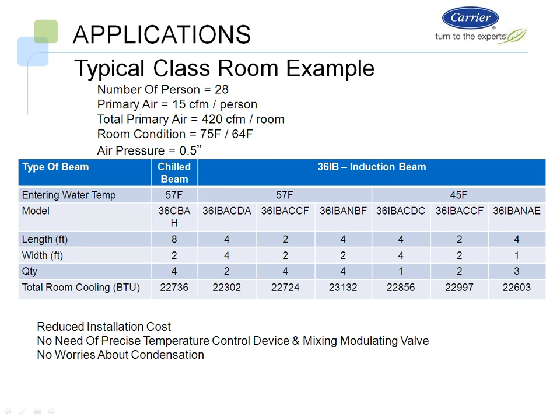And what we did here is put a simple application comparison up for you. So, a typical classroom with about 28 people, primary air of 15 CFM per person, so you have total primary air of 420 CFM for the room, with a room condition of 75 dry bulb, 64 wet bulb, and let's say the operating static pressure is about a half inch. So if I look at a traditional chilled beam, sensible only, at 57 degrees, and we happen to offer those, there are Carrier units there, it would require 4 8x2 type sensible only chilled beams. Now, if I take that same condition at 57-degree water and use the 36 IB, which is our new induction beam, and if I were to use a 4x4 unit, I would only need 2 in a sensible only application as well. So if you think about that, I get the same total room capacity.